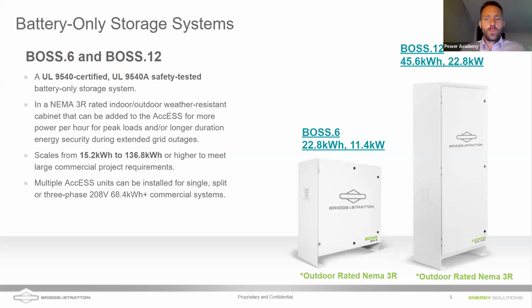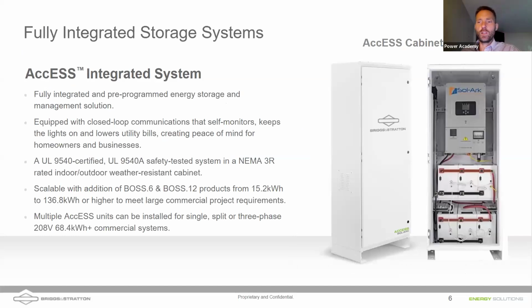So I'm showing on the screen here are Boss 6 and Boss 12 cabinets. These are UL certified, 9540 certified, and 9540A safety tested cabinets. They're NEMA 3R rated outdoor. There's a temperature controlled fan on those cabinets. And we have these with options to integrate heaters if that's needed in your location. And we can also integrate an inverter into the top of that Boss 12 cabinet to have kind of an all-in-one plug-and-play option like is shown on the screen here. So this is what we're calling an AccESS cabinet. We can do that with a Sol-Ark inverter, a Schneider inverter, etc. We unfortunately cannot put the Sol-Ark 15K inside the enclosure just because the 15K puts out a little bit more heat than we would want in an enclosure.